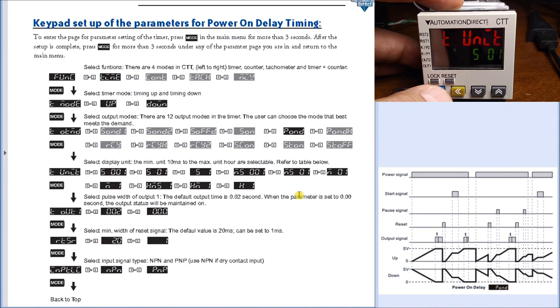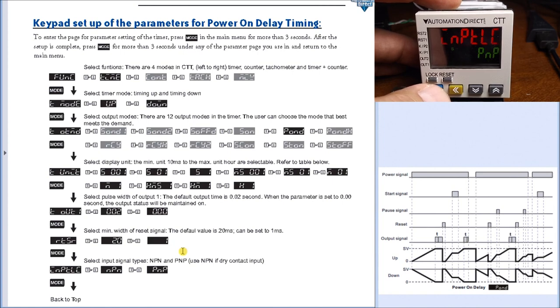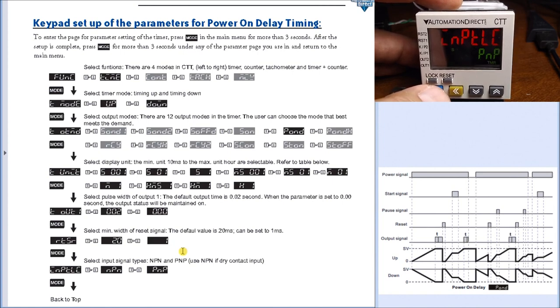Next we have our timing units, in this case here we have 0.1 of a second. Next we have our output, now we set for zero so the outputs will be maintained. Then we have our reset value which is set for 20 milliseconds, and then we have a PNP because we're connected to a voltage input in our particular case here.